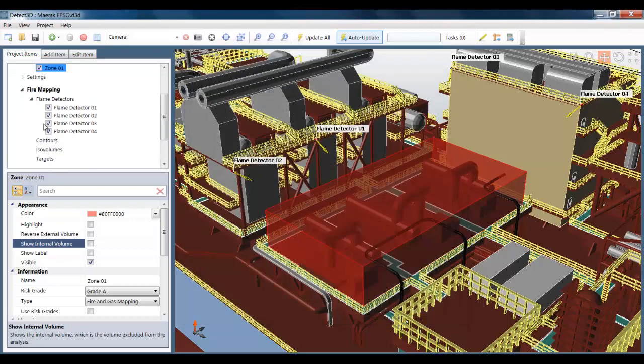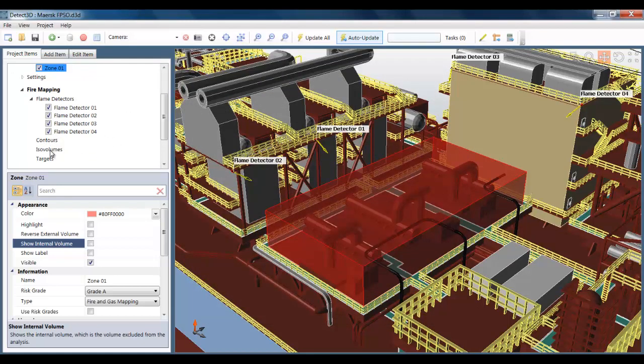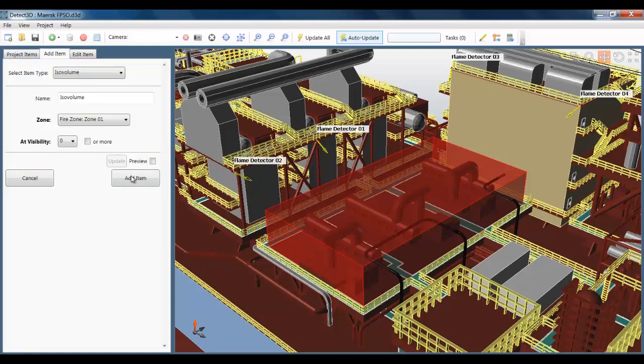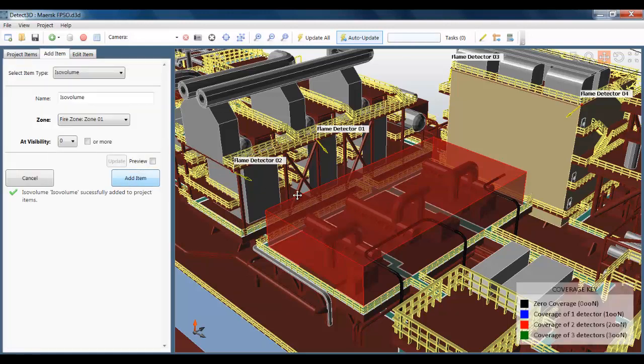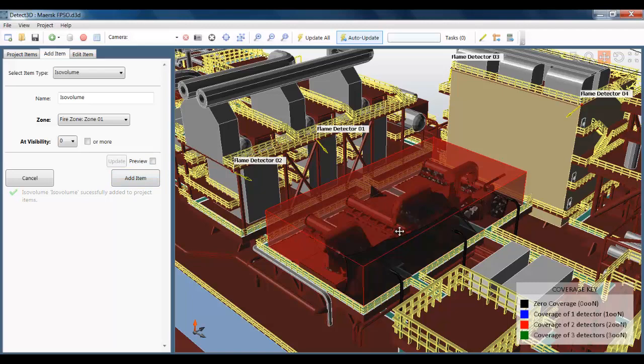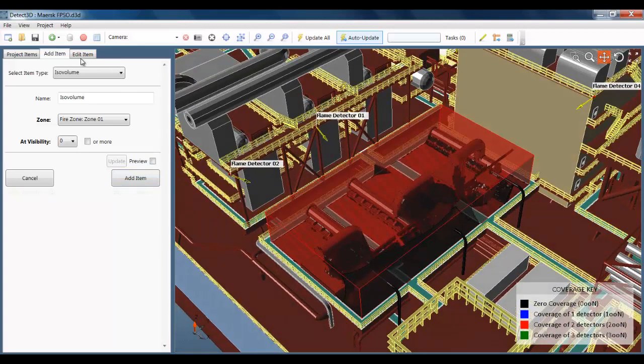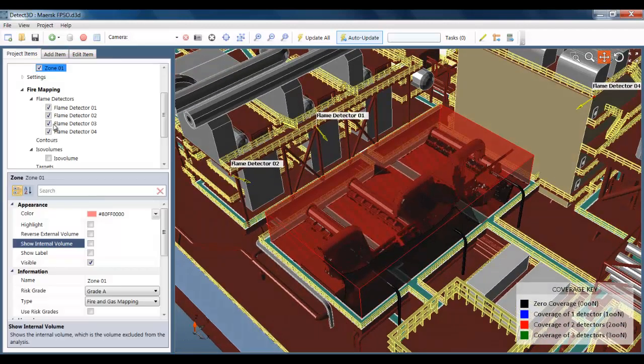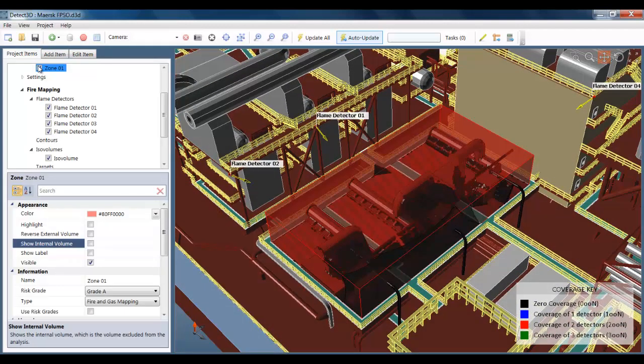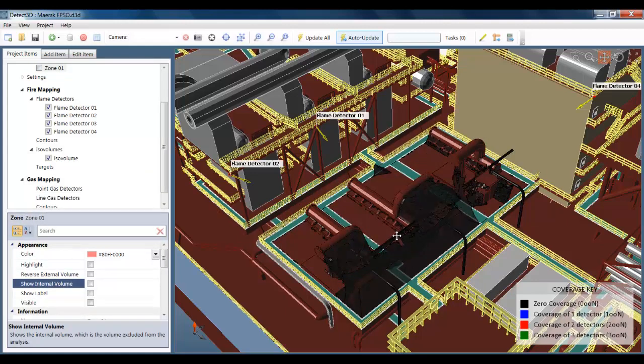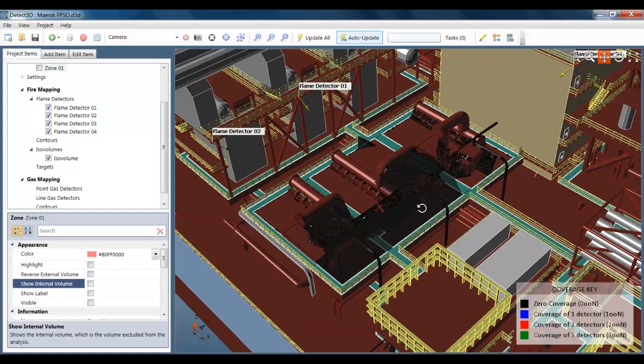It's also calculated the coverage statistics already for that fire zone. We can see it's 14% zero coverage, 85% one or more, and 44% two or more. As usual, we can visualize the results using ISO volumes. And here I'm just adding one at zero visibility, which is showing the blind spots in the fire zones. You can see that the ISO volume was added virtually instantly to the project. And this is because the calculation of the ISO volume is really unaffected by the complexity of the geometry.